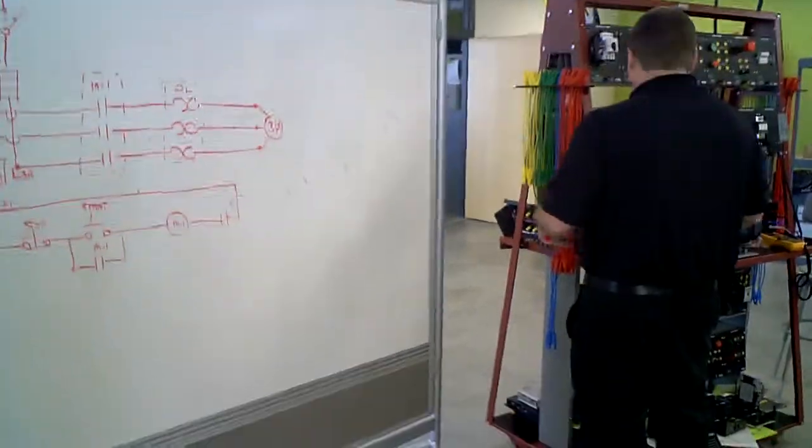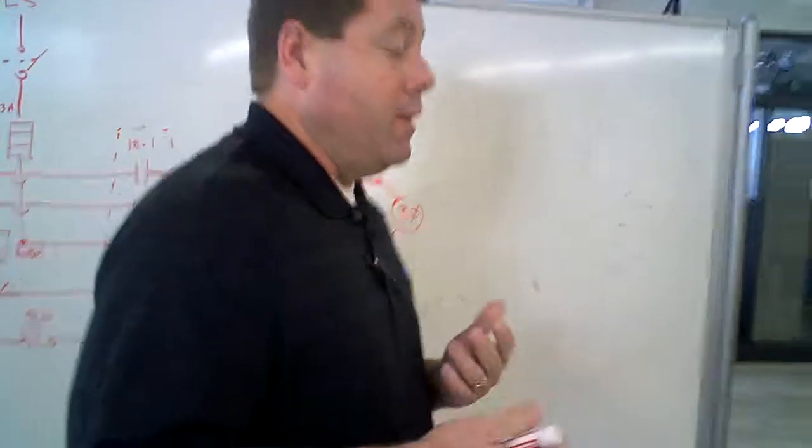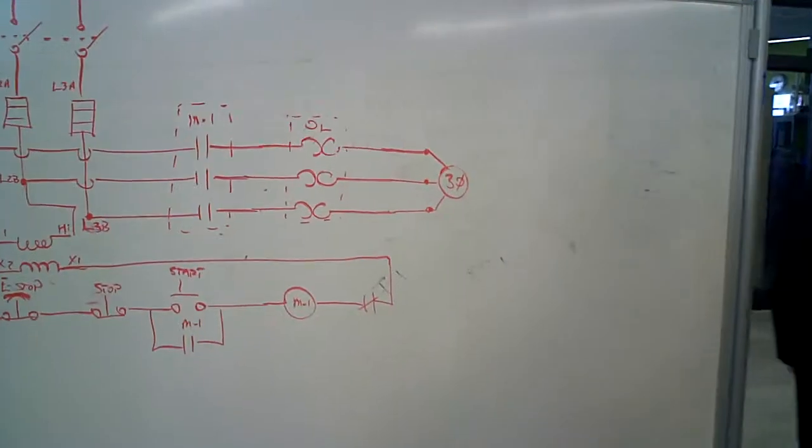And you have your motor sitting right here, and this is shown as a three-phase motor. This is actually a nine-lead Y-connected motor, and we'll talk about that in just a little bit of how to troubleshoot that or how to wire it up.